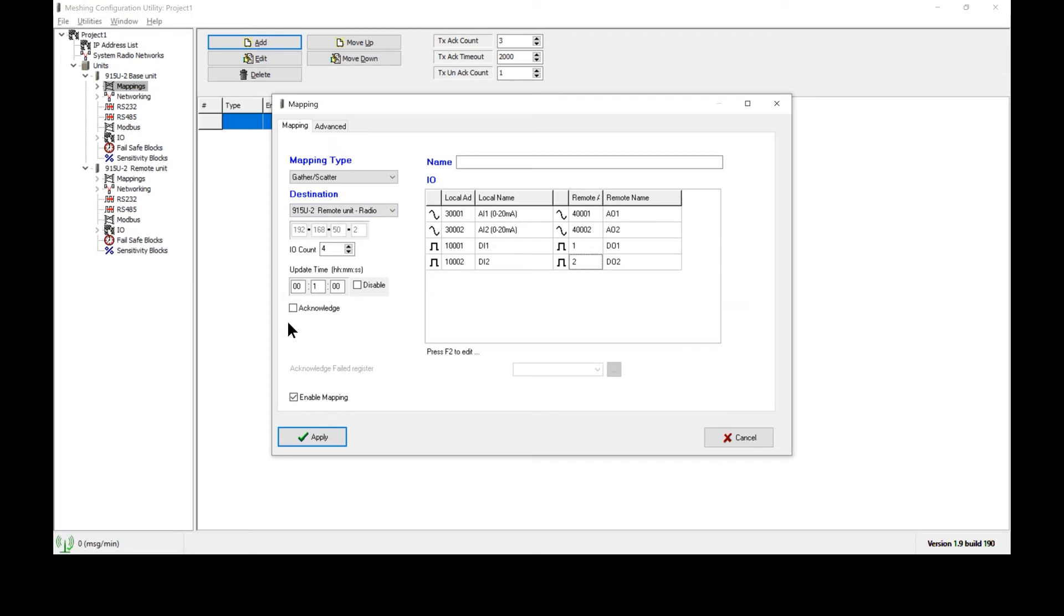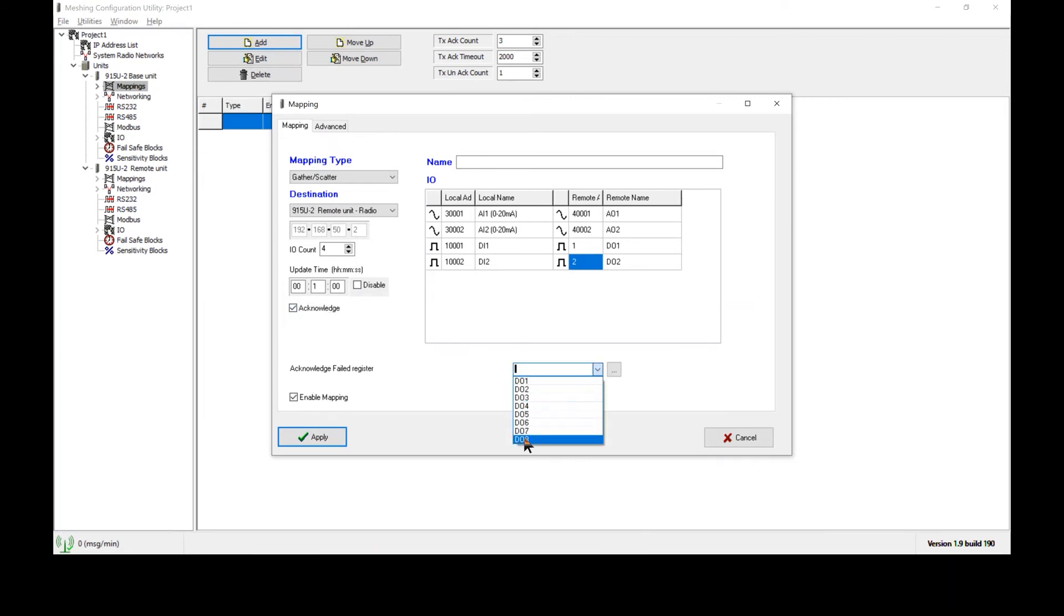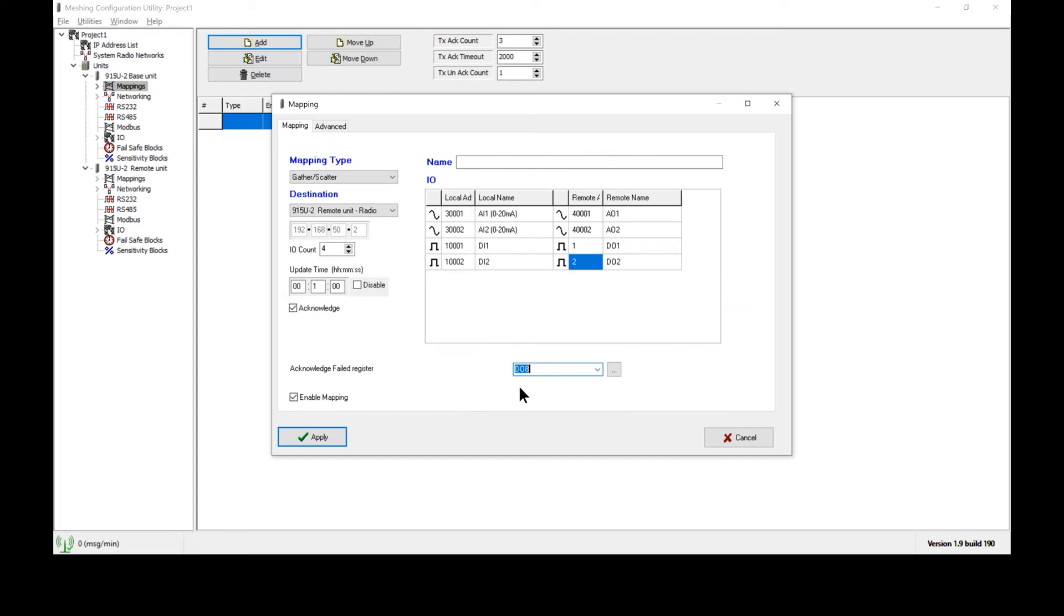Now what we will do is we will set a communications failure indication by clicking acknowledge. Now we have these acknowledge failed registers available, and I am going to use digital output eight to indicate that if this message failed to transmit. Digital output eight has an LED that is directly next to it on the terminal block of the radio, so you can observe that LED's status to determine if communications are successful. If communications are successful, do eight will be off, if they have failed, do eight will be on.